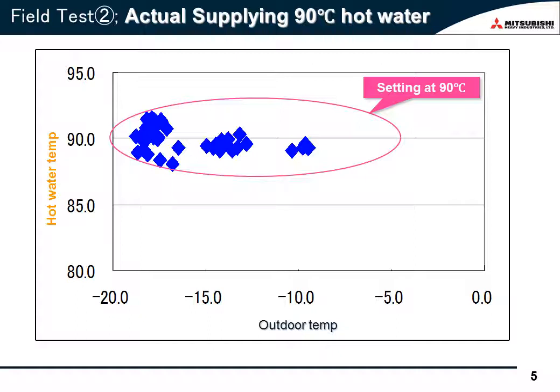I'd like to talk about the other actual performances. This slide shows the actual hot water temperature, with the horizontal axis representing ambient temperature. You'll see Q-ton really makes hot water at 90 degrees Celsius under about minus 20 degrees Celsius ambient temperature.